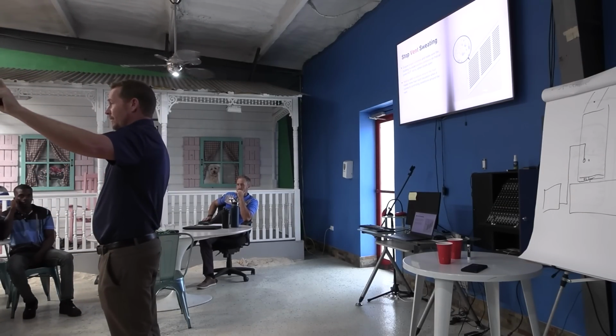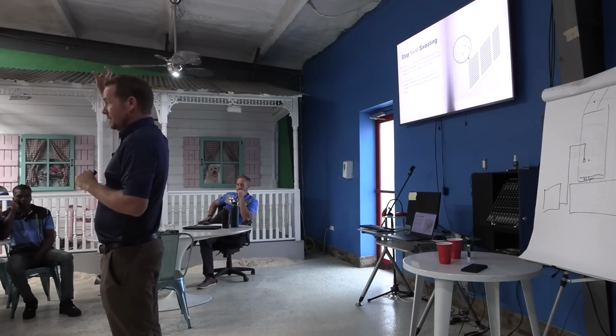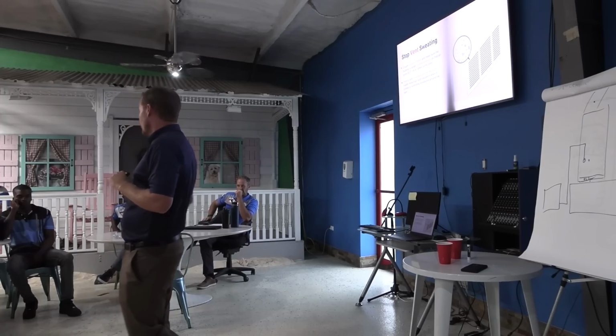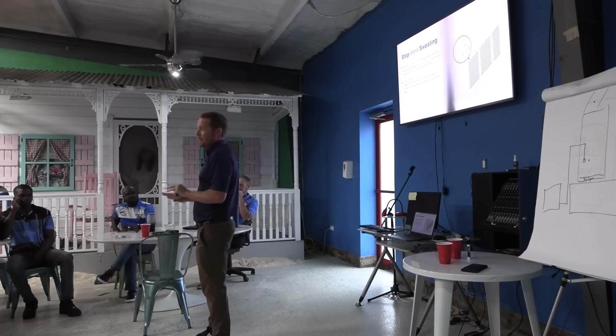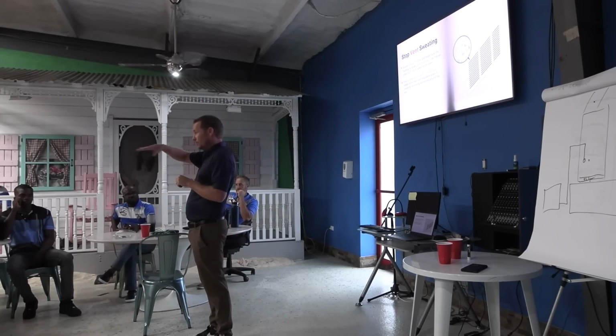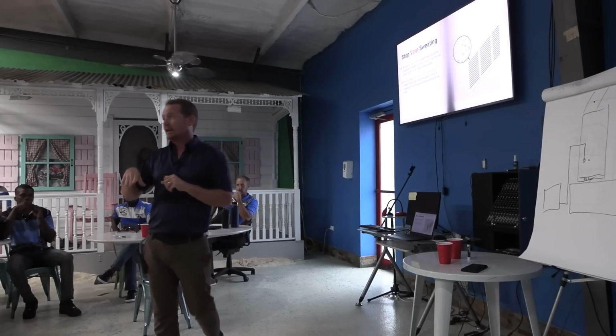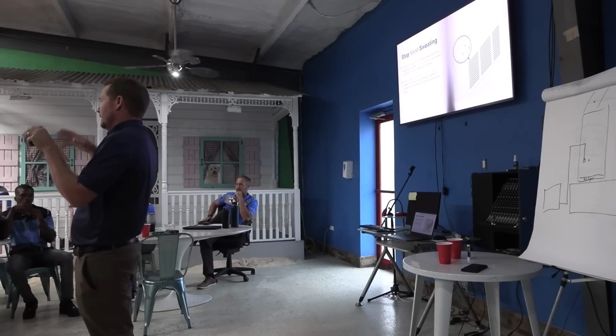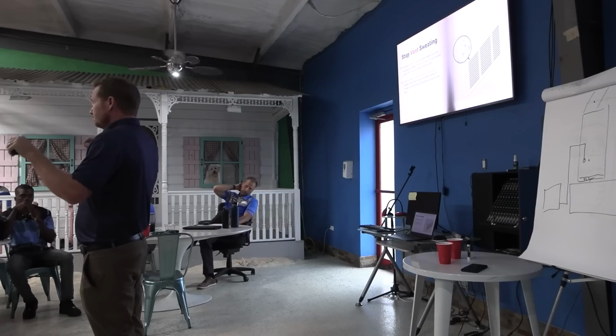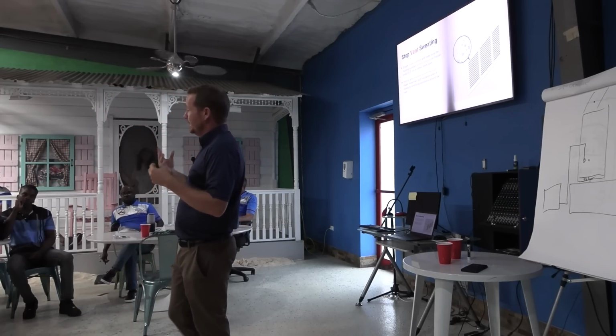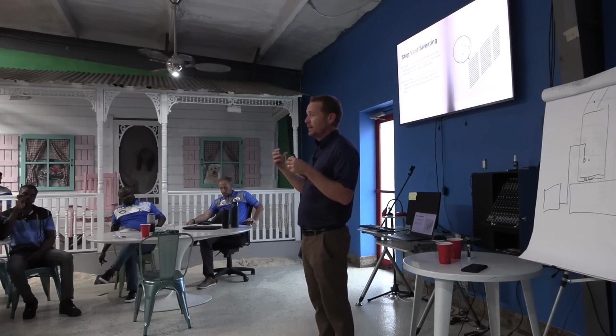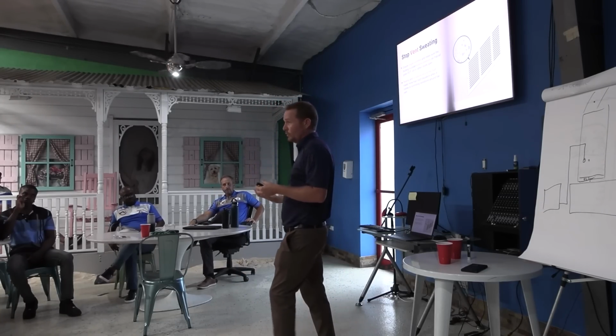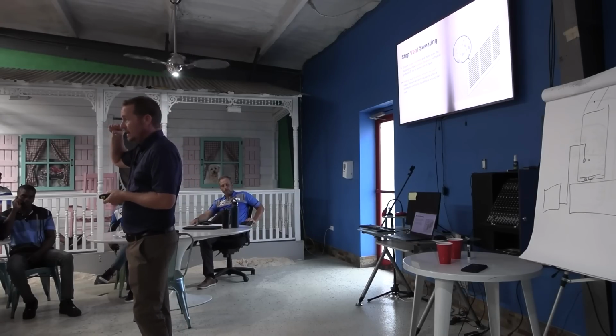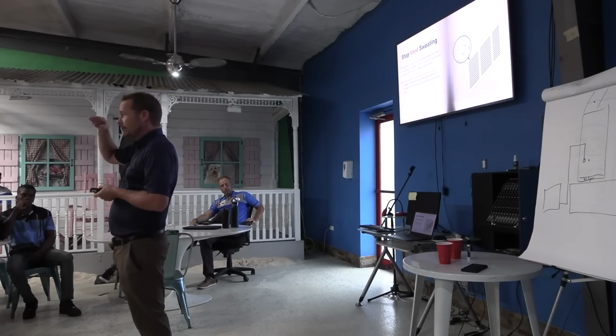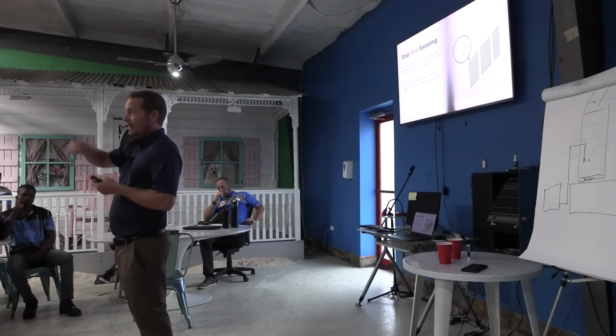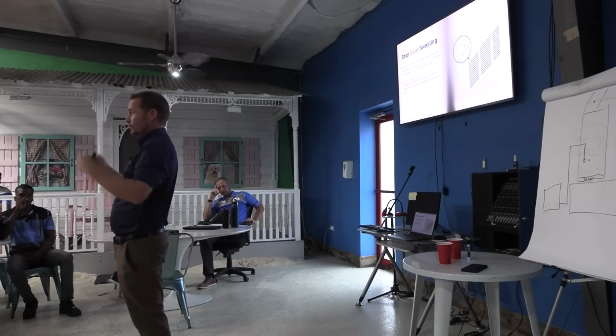And what do the Japanese care about? They care about getting really high SEER ratings because that's what people buy them on. So run away from 30 SEER ductless systems, run away, run away. Bad dehumidification. If you look at the stats, the actual dehumidifying capabilities of those systems, sometimes they are absolutely terrible. Sensible heat ratios, which we're not talking about here, but terrible, terrible. So more and more manufacturers like Daikin and Atmosphera with their Atmosphera line or whatever, they're starting to catch on that the way to make ductless systems work really well and be good dehumidifiers is just peg that coil temperature as low as you can get it. So peg it to 40 degrees or lower, just run it that way, and now when it stages up and stages down, it just runs a cold coil.